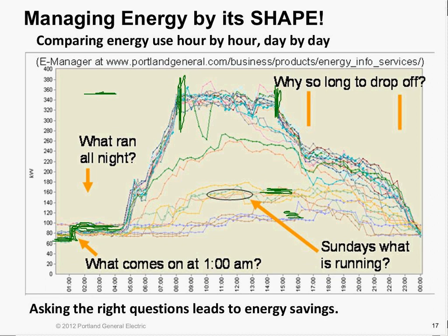What that means is if you bought the better software, you could drop this chart, 365 days a year, and save all this energy in here. All this could go away and the shape would change. And you can do the calculation of hours at the bottom and kW at the left. You can calculate exactly how much savings that is and show it graphically. And you can also say if that stops happening, then the software is not working. So monitoring load in the form of shape and looking at blocks of energy like this can be a great way to use the formula, but the results are shown in a graph.